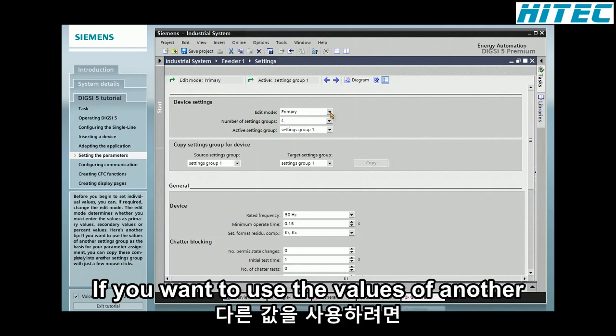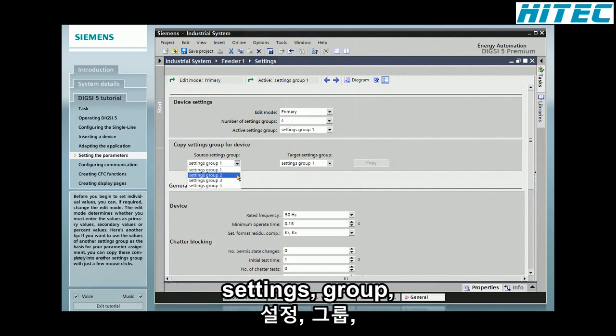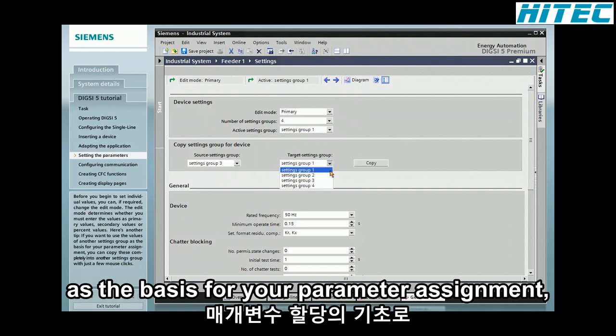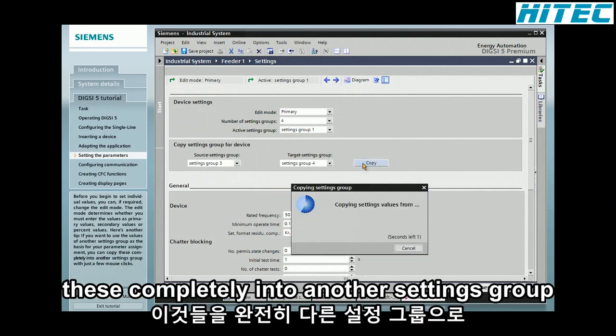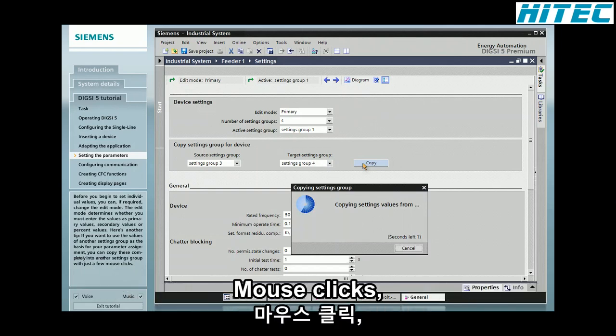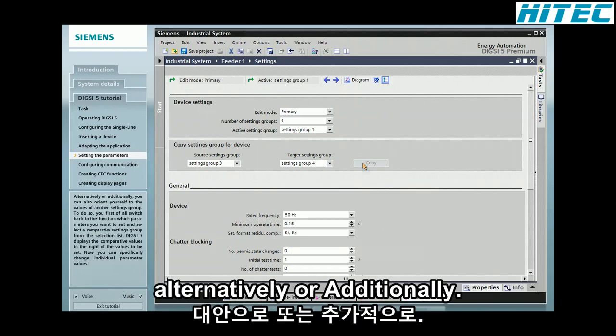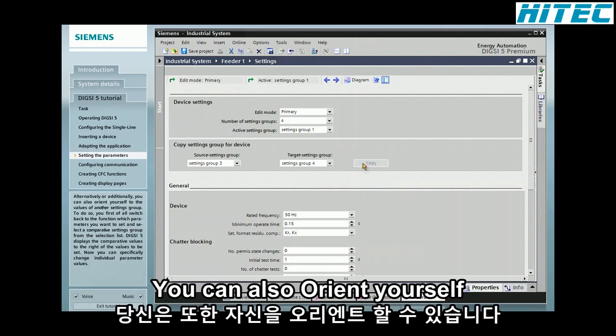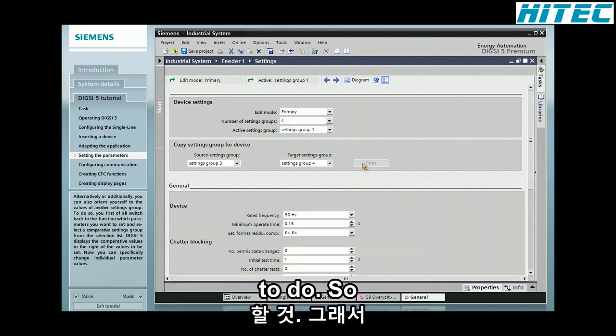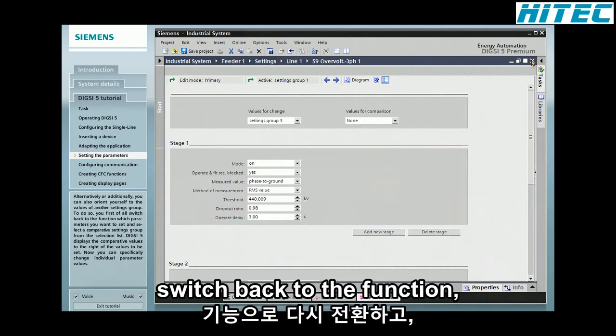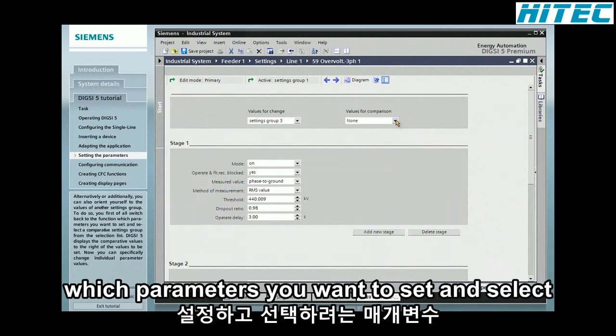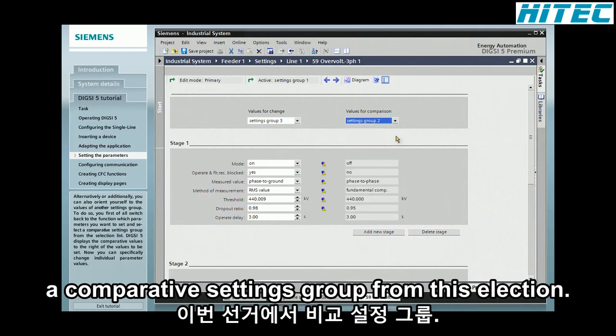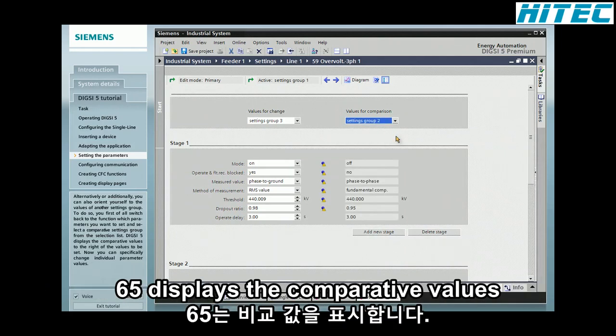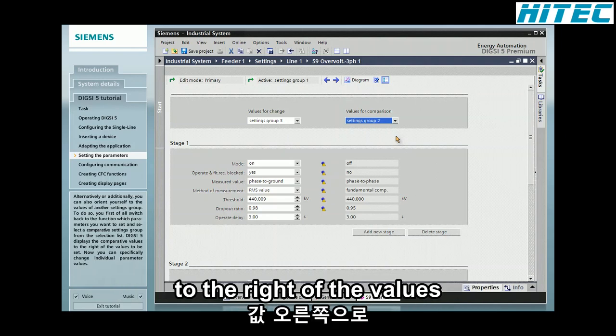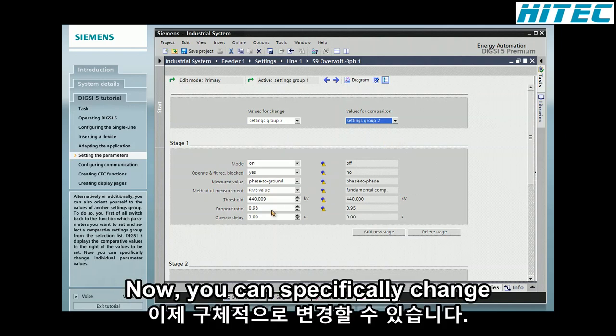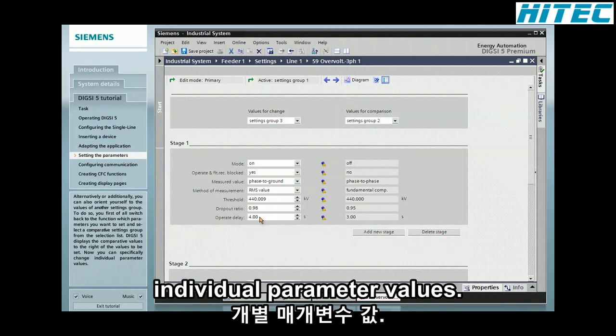Here's another tip. If you want to use the values of another settings group as the basis for your parameter assignment, you can copy these completely into another settings group with just a few mouse clicks. Alternatively, or additionally, you can also orient yourself to the values of another settings group. To do so, you first of all switch back to the function whose parameters you want to set and select a comparative settings group from the selection list. DIGSI 5 displays the comparative values to the right of the values to be set. Now you can specifically change individual parameter values.